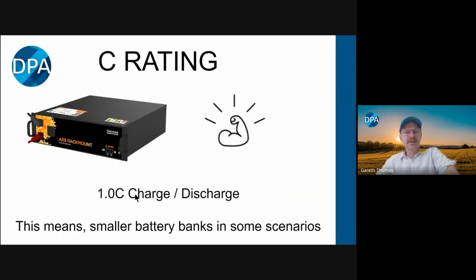The C rating of the battery is 1C, so the maximum it will do is, for a 100 amp hour battery, 100 amps. This means in some scenarios you can have a smaller battery bank, like for a hybrid generator or something similar. But in general you're not going to design it to do 100 amps continuously—you'll design for about 70% of that, since you don't want to run it at that top threshold. And of course, it's got surge capability over and above that for 10 seconds.